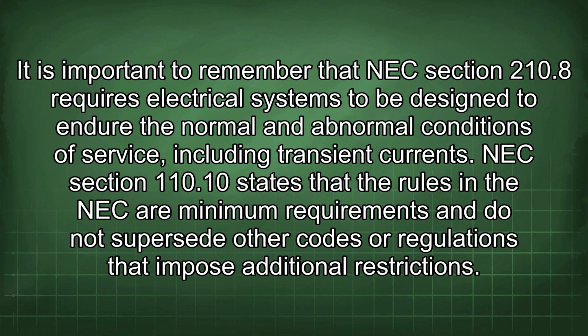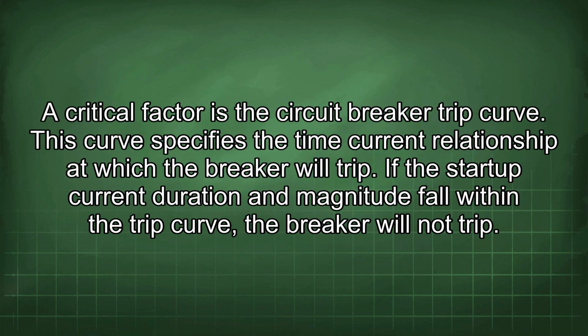It is important to remember that NEC Section 210.8 requires electrical systems to be designed to endure the normal and abnormal conditions of service, including transient currents. NEC Section 110.10 states that the rules in the NEC are minimum requirements and do not supersede other codes or regulations that impose additional restrictions. A critical factor is the circuit breaker trip curve. This curve specifies the time-current relationship at which the breaker will trip. If the startup current duration and magnitude fall within the trip curve, the breaker will not trip.